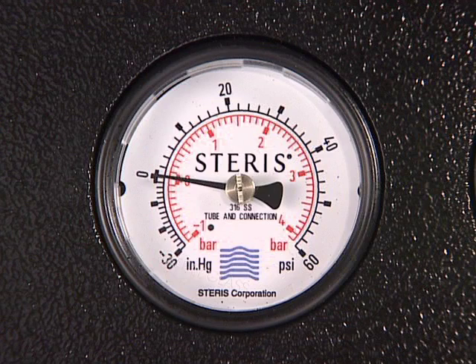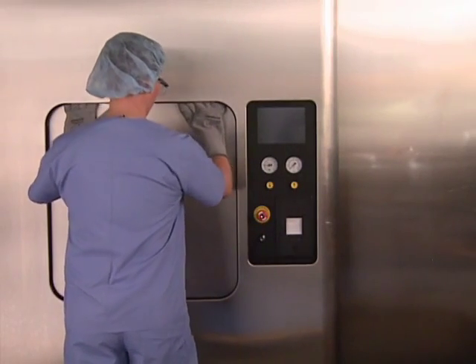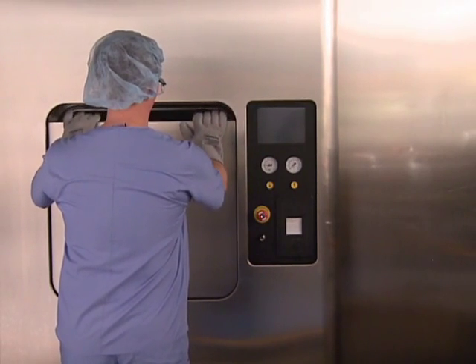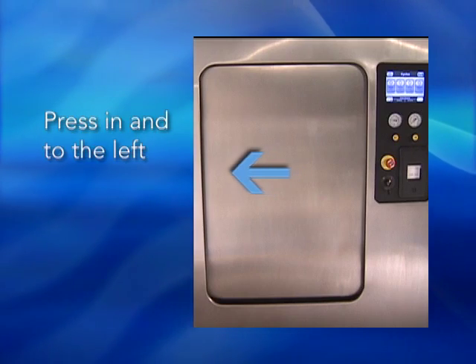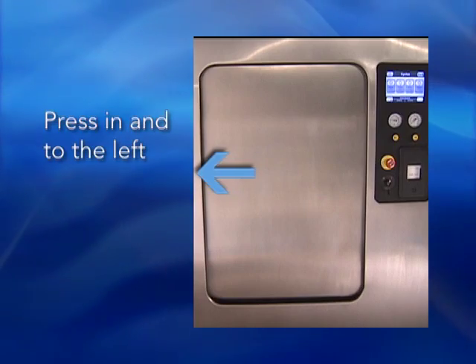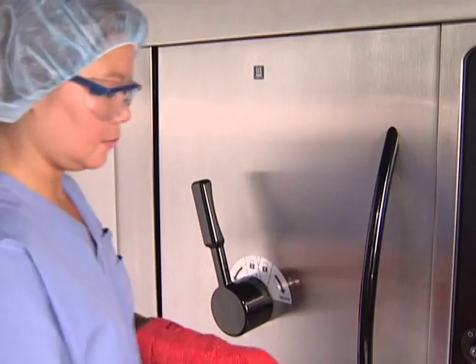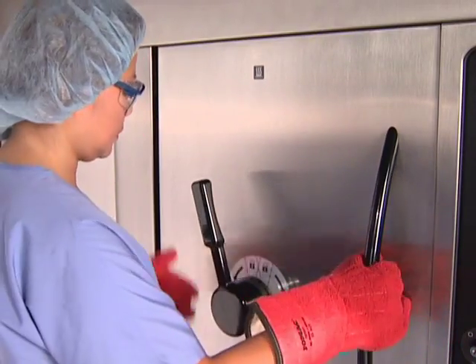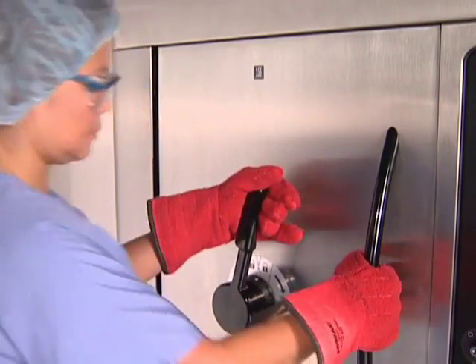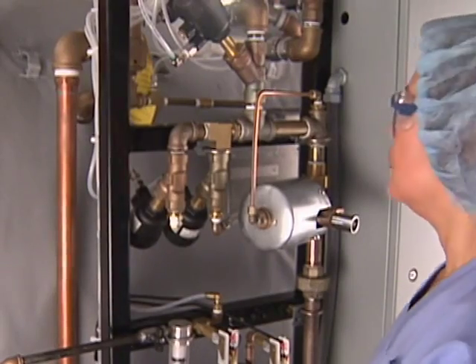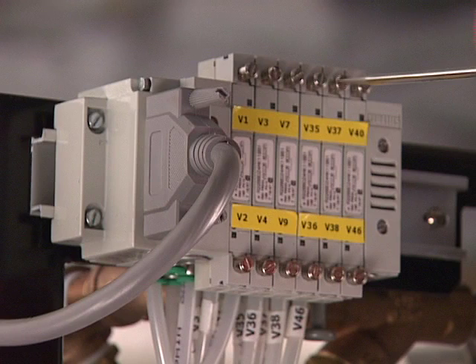When the chamber and seal pressure reach 0, you'll need to manually open the door to release any remaining vapor and heat. For vertical sliding door models, press the door inward and down. For horizontal sliding door models, press the door inward and to the left. And for hinged door models, unlock the door as usual. Next, set screws on manifold back 1/4 turn after emergency exhaust.